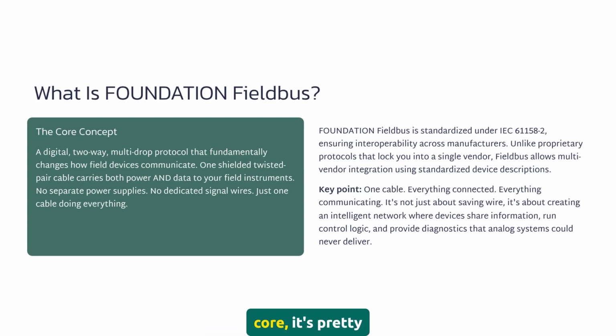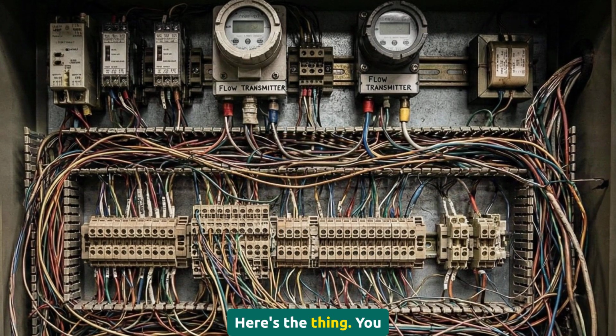So, Foundation Fieldbus? Look, at its core, it's pretty elegant. You take one shielded twisted pair cable. One. And that cable carries both power and data. Not some light-duty power, we're talking about feeding your field transmitters, your solenoids, and your instruments without a separate power supply. It's a digital, two-way, multi-drop protocol. IEC 61158-2 standard.